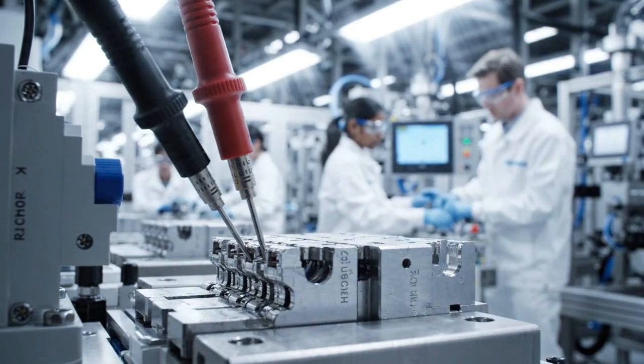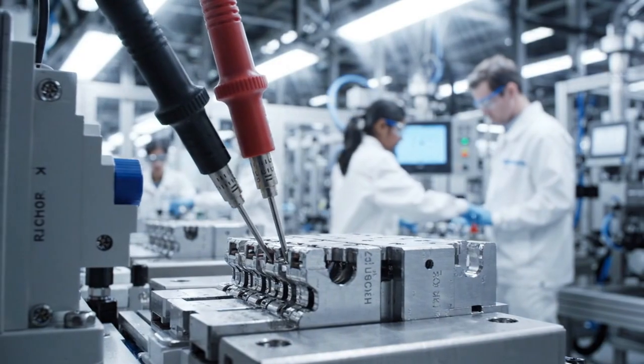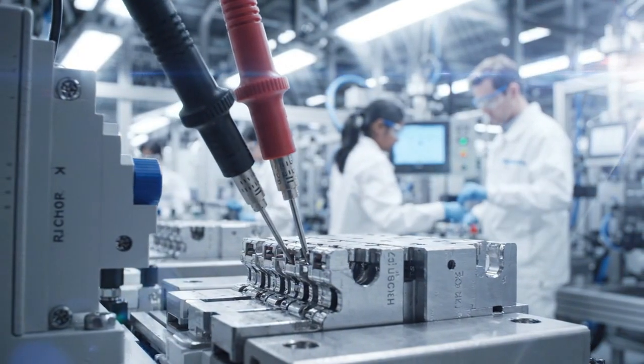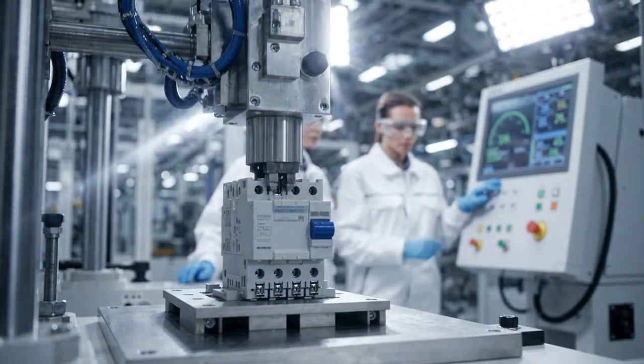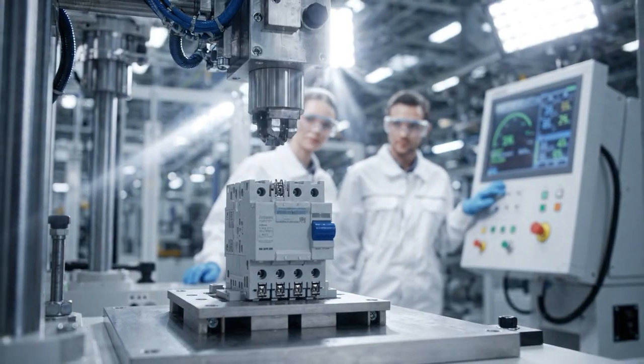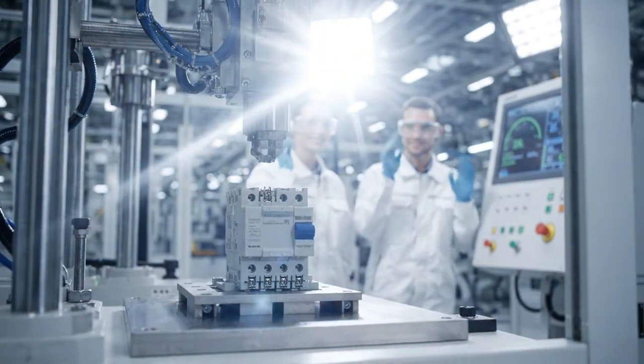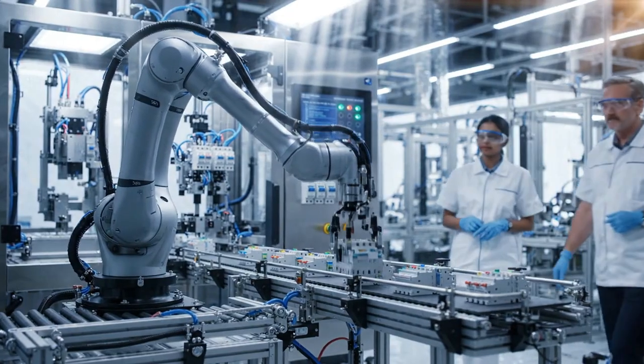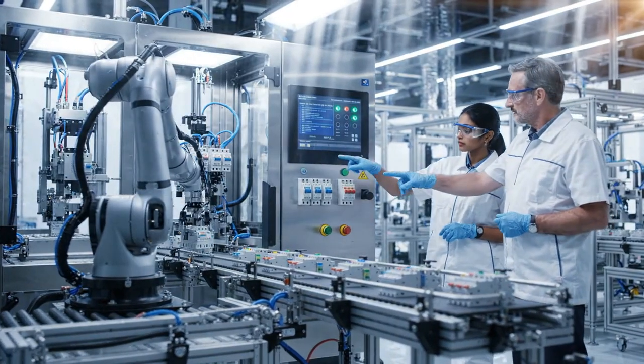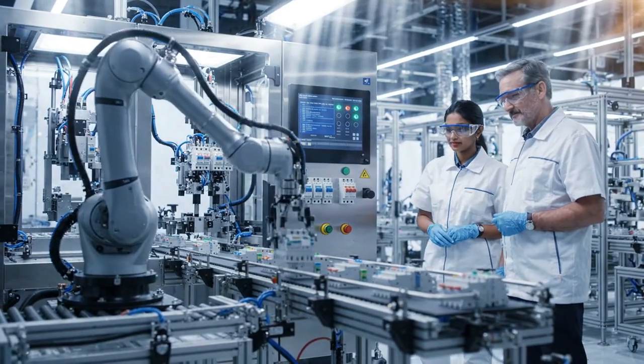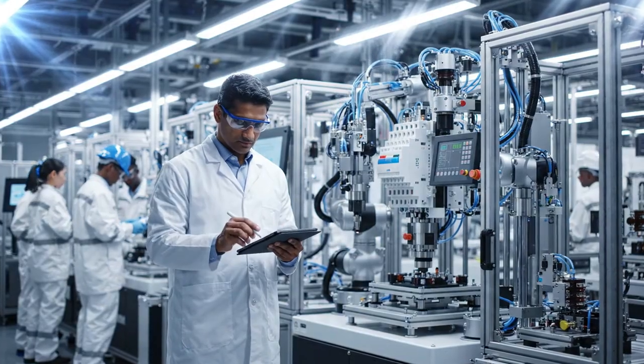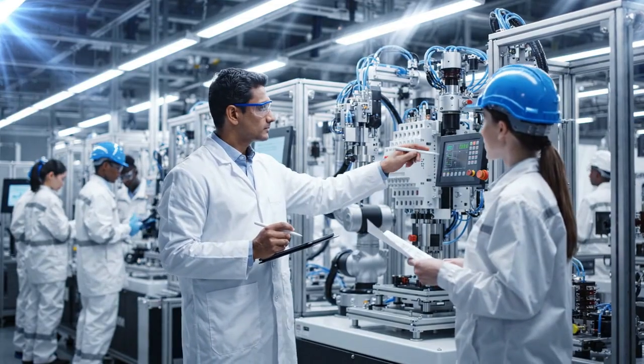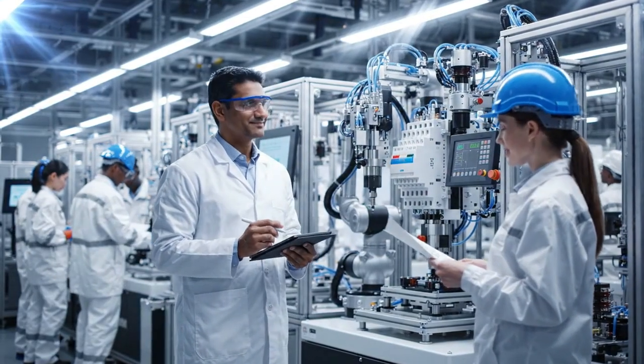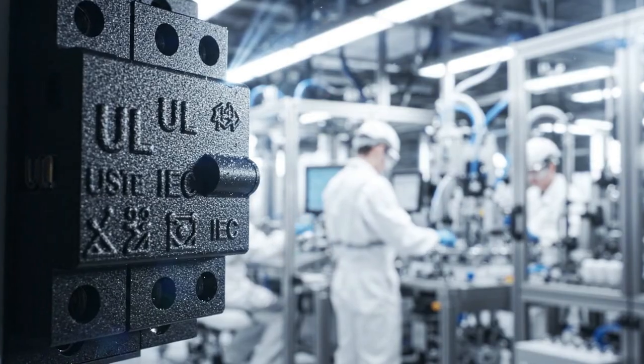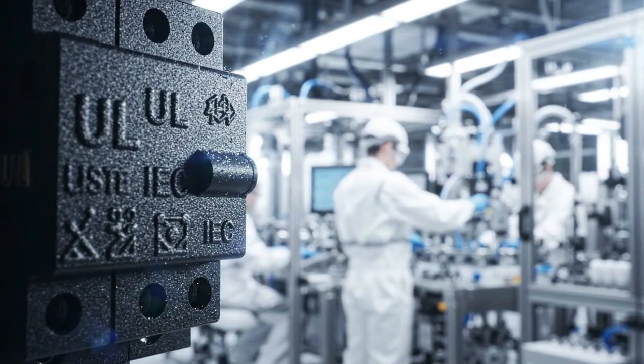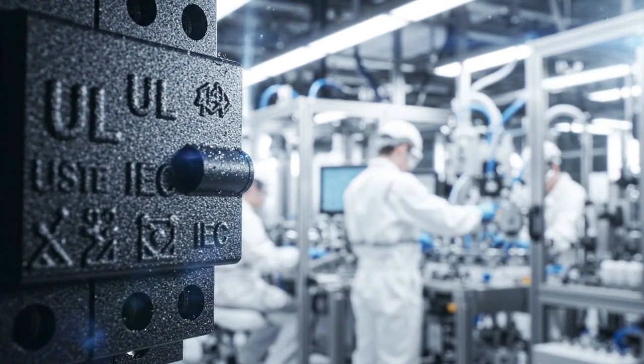Contact resistance must remain low throughout the breaker's operational life. Rising resistance indicates contact surface degradation that increases heating. Quality audits verify that production quality remained consistent over time. Random sampling provides statistical confidence that every breaker meets specification. Independent certification requires periodic factory inspections and witness testing. Certification marks on the breaker prove compliance verified by an independent authority. Certification marks represent thousands of hours of testing and millions of dollars of qualification investment. They assure installers and consumers of verified safety performance.